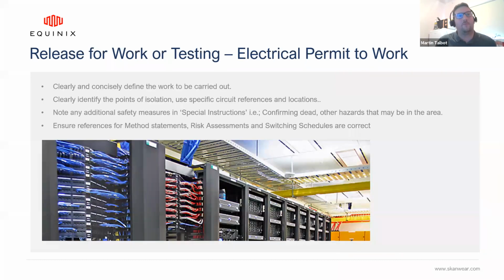So on that permit, we want to clearly and concisely define all the work to be carried out, identify the points of isolation, and use specific circuit references and locations. You need to know any additional safety measures, such as special instructions, exactly like the confirming dead procedure that I just described, where our worker proves dead with full arc flash PPE within the arc flash boundary, and then goes and confirms dead with arc flash restrictions relaxed to a contractor who doesn't have the same type of equipment that your employee may be supplied with.